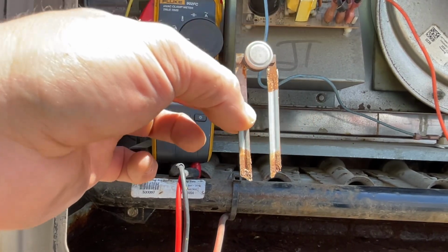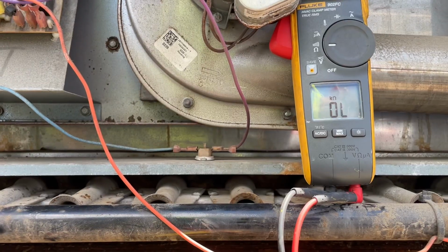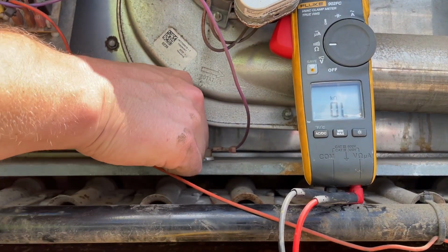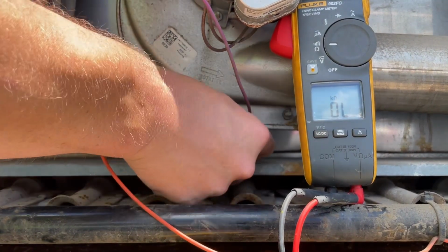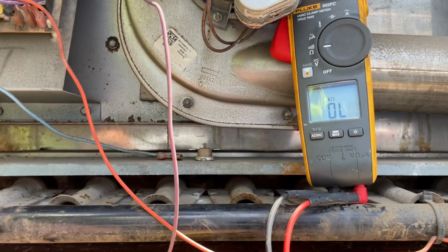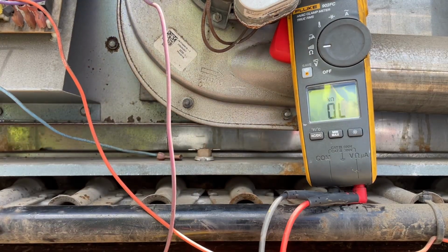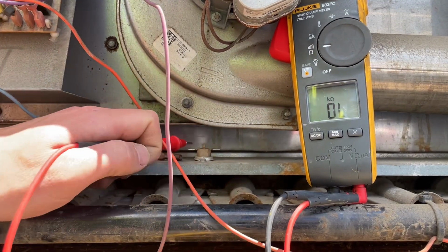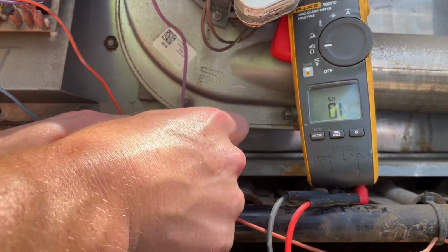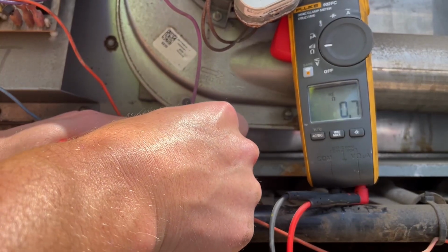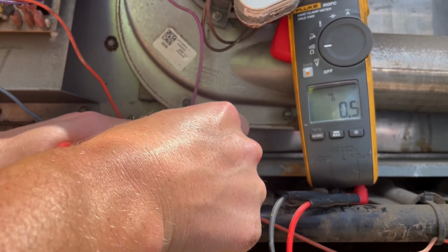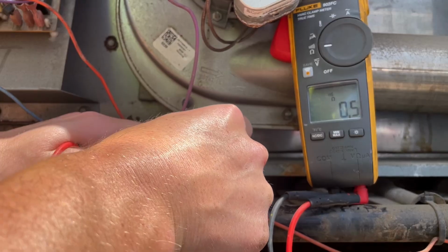We'll check the rollout as well now. All right, let's check our rollout switch now. Power's off. We're just gonna pull our leads off either side. Meter's still in continuity, ohms, resistance. We're just gonna go across and we are good. We have continuity through our rollout switch, which is great.